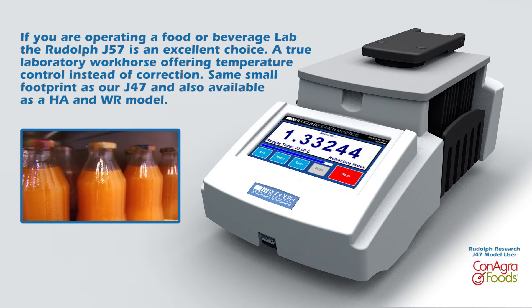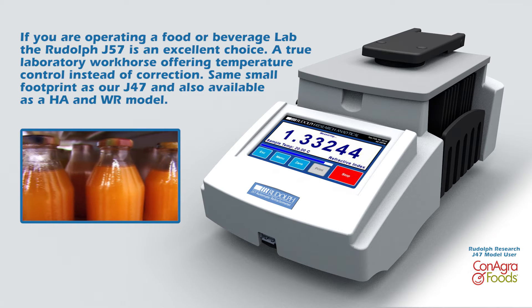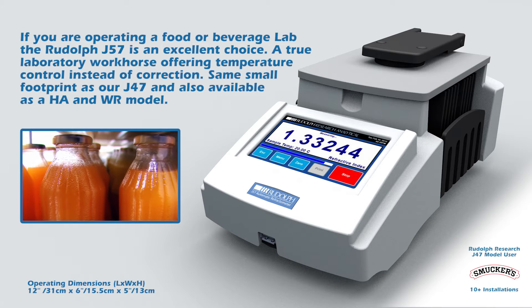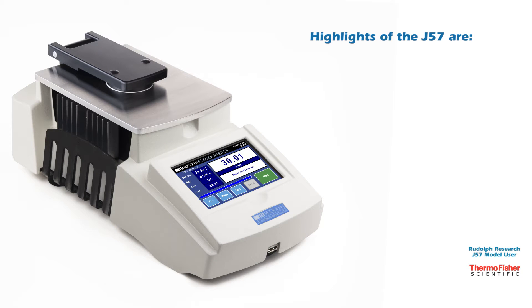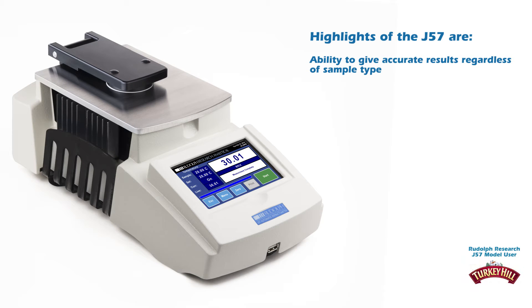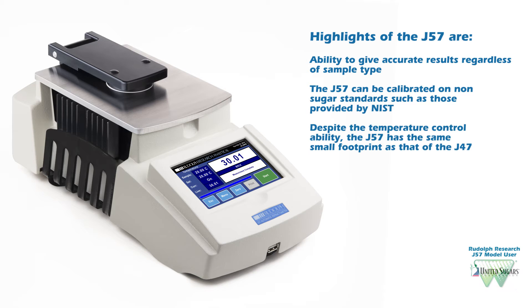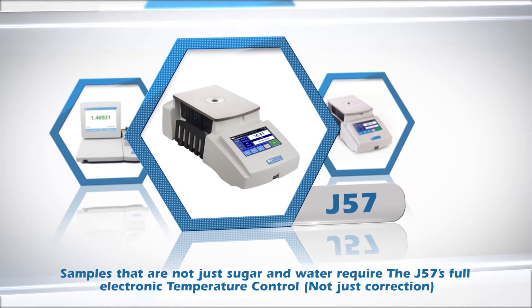If you're operating a food or beverage lab, the J57 is an excellent choice — a true laboratory workhorse offering temperature control instead of correction. It has the same small footprint as the J47 and is also available as an HA and WR model. The J57 gives accurate results regardless of sample type and can be calibrated on non-sugar standards such as those provided by NIST. It is a perfect choice when your samples are no longer just sugar and water based.